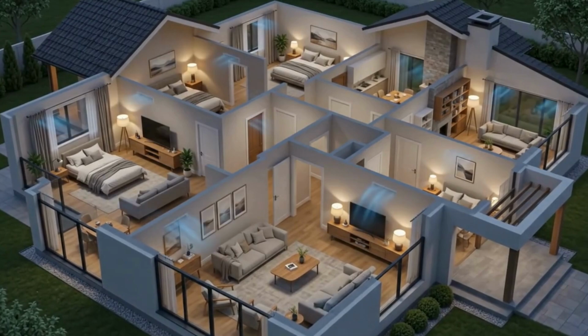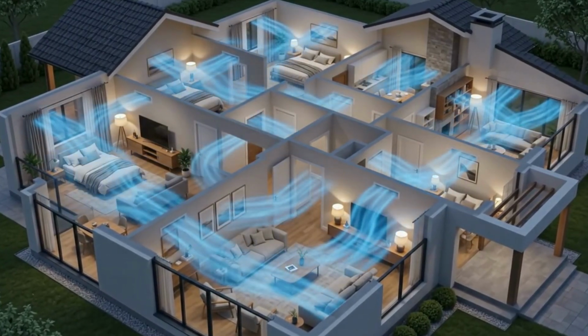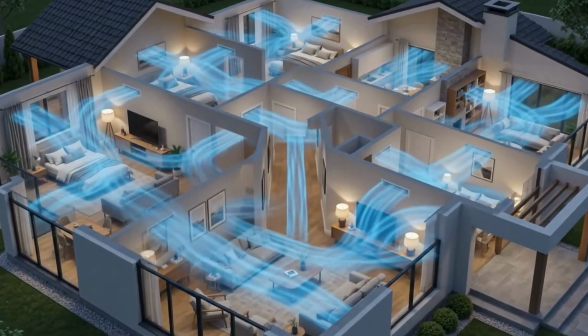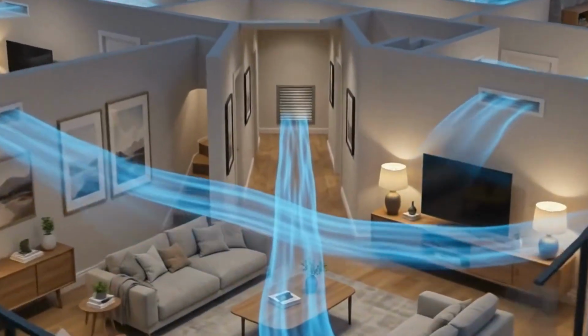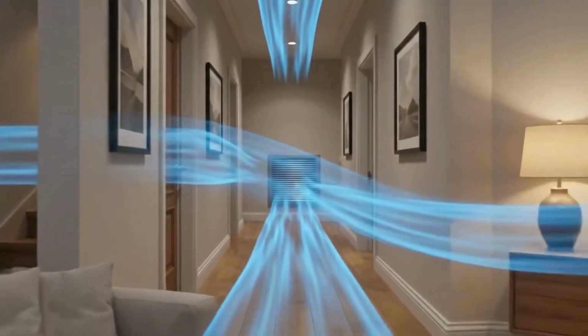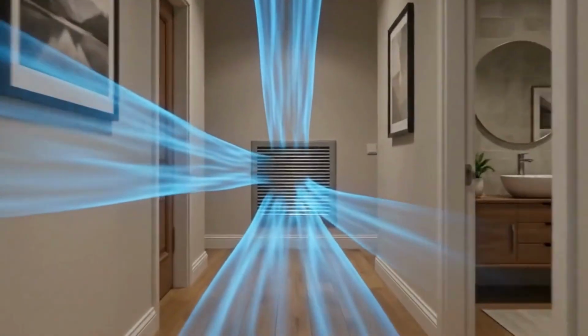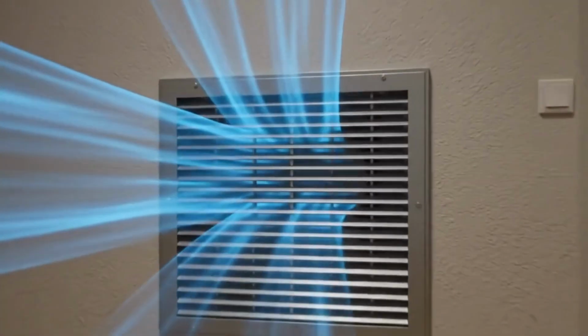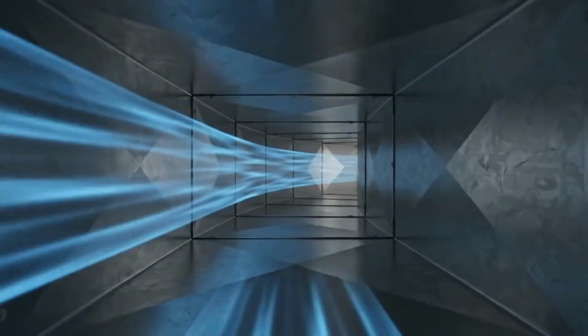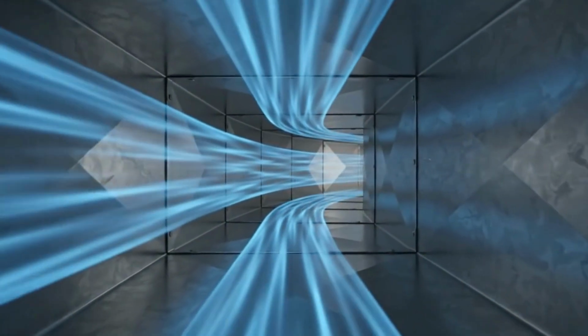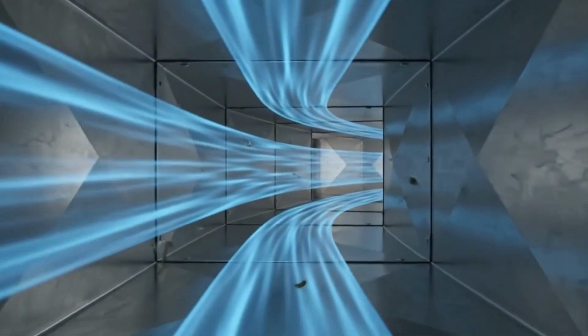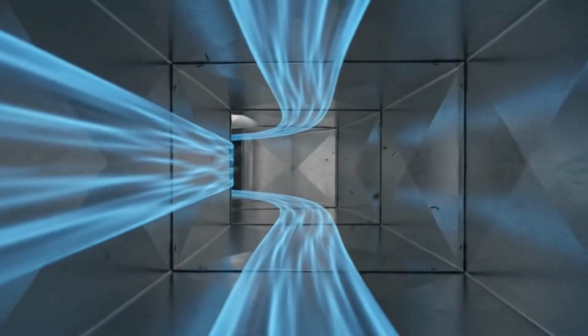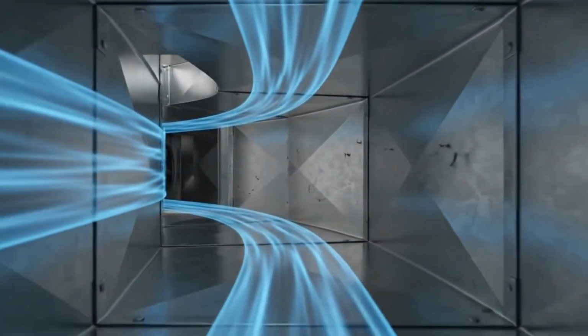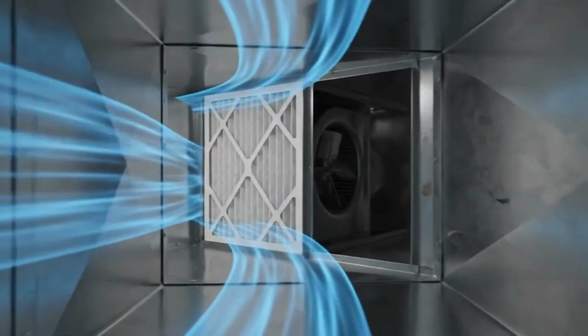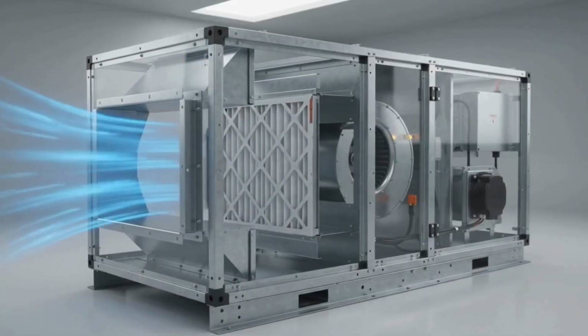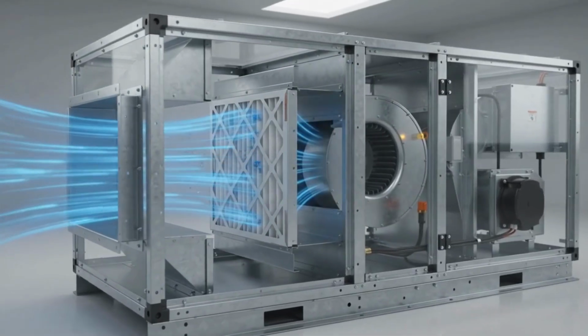Now, there's all kinds of different ideas and thoughts out there, but think about it. Where is the last place the air goes into from our house? We have air in our house. It gets sucked into the return, goes into the air handler, down, up, and through, and then enters the bottom of the air handler. You could have an inverted air handler, what's called a downflow, but that would be the top. So think about this. If I want to filter out particles, wouldn't I want to filter the particles at the last possible location before the air enters the system?